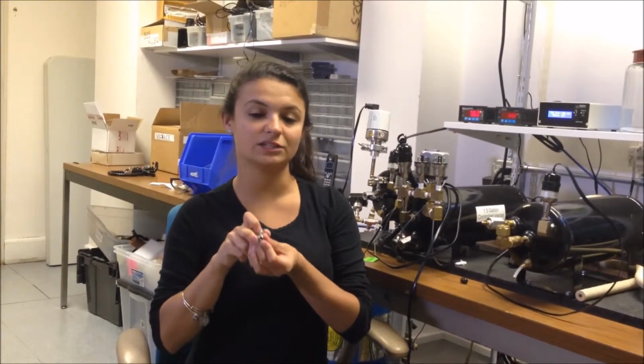If there's a visible sign of oil pouring out of the open end of the tube, or your reading is too low or too high for the expected pressure range, those could also be signs that the tube is contaminated. There are many ways to fix and clean the tube, and we're going to show you how. So you want to see how we clean a thermocouple tube?